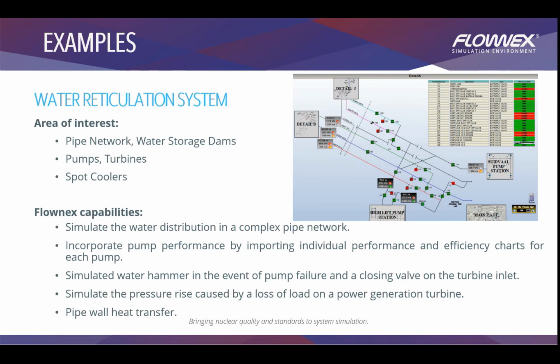So this is one of the examples where we had a water reticulation system in South Africa for one of the companies, where we modeled the entire system for them in Flownex and showed them where they will experience pressure drop, where they will experience less flow, or they'll have high velocities in the pipeline. So we managed to get all those in Flownex as well.